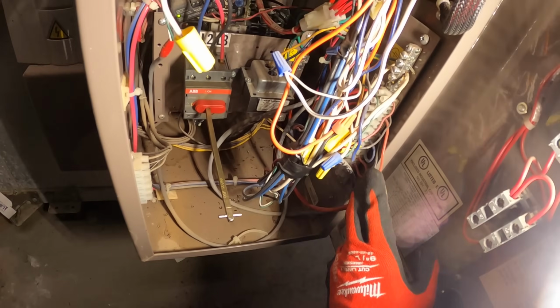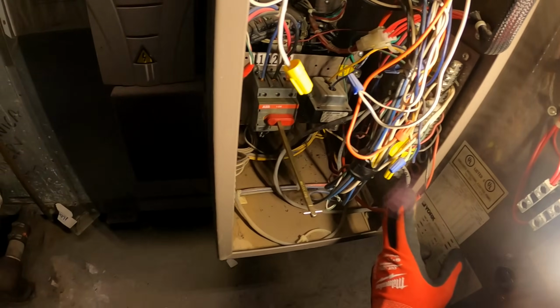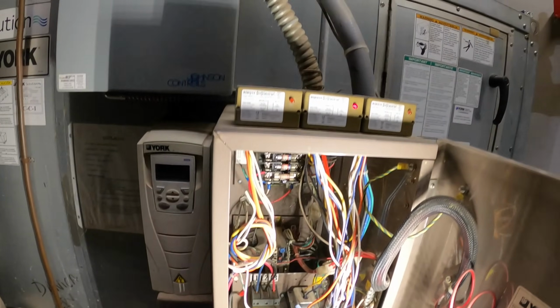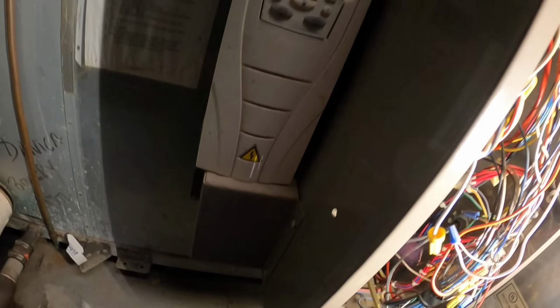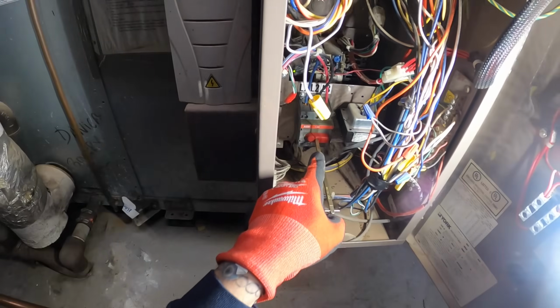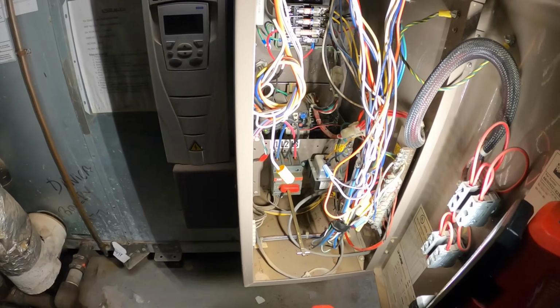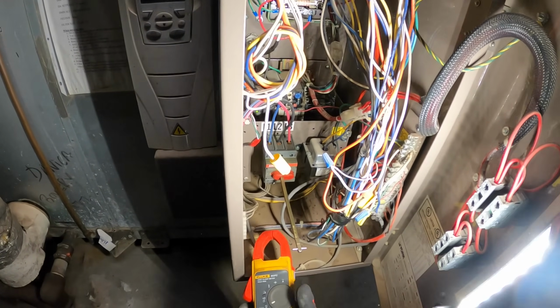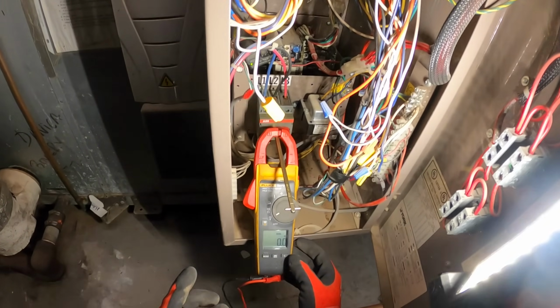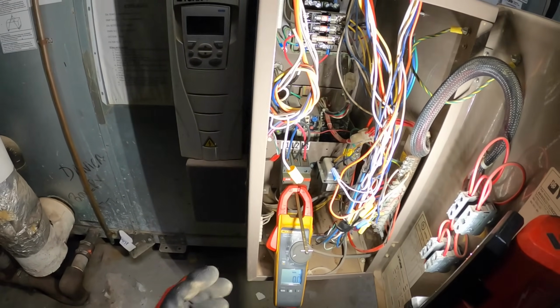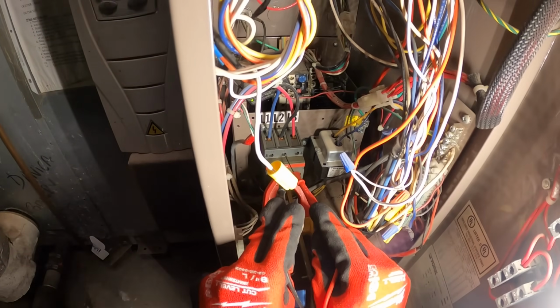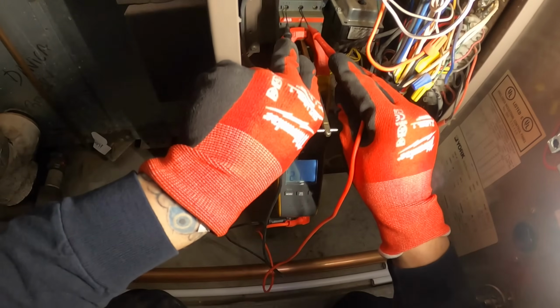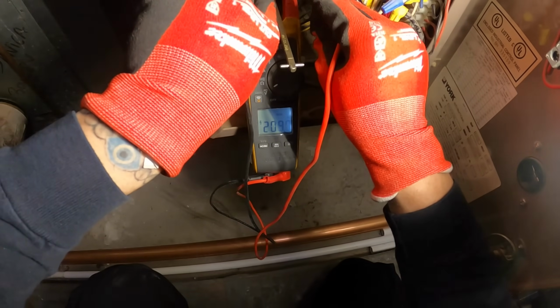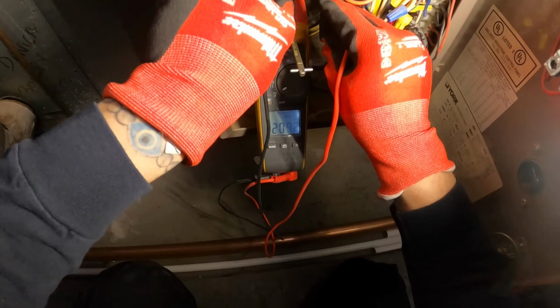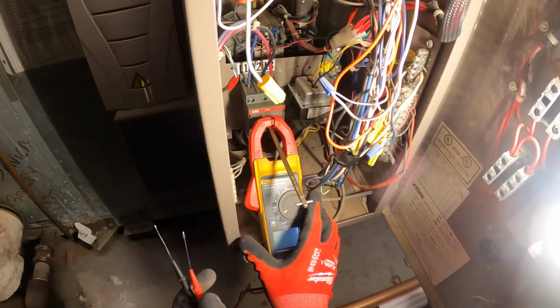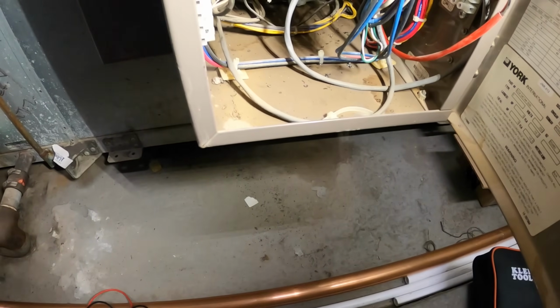Those 2 wires come in right here. We could probably check over there, but let's start with main power. This is the main power coming in. I see those wires. Where is it going to? Comes in right here. Let's see, volts AC. It's a three-phase system. We got 3 wires. Got 208 from L1 to L2, L1 to L3 we got 208, and L2 to L3. All right, incoming power is there, so we can rule out the breaker.